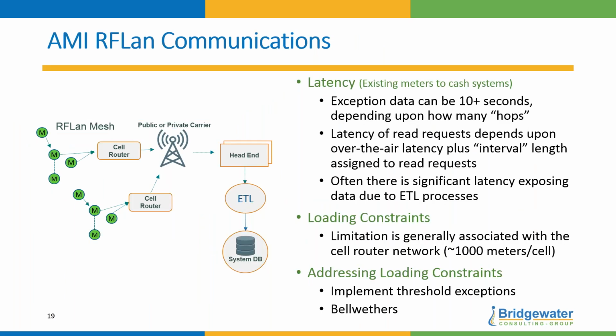Now, RF LAN communications do have some limitations. Latency. To give you an idea, depending upon how many hops the meter is away, it can be 10 seconds before data comes back from a meter to the head-end system. Okay? That's number one. Many times it's quicker, but it can take that long. When you do major read requests, you have to do an interval, so that interval can be 5 minutes, 10 minutes. So you can have a latency of information coming back. And also there's the ETL, extract, transform, and load process by the time it gets to the database. So there are inherently some limitations.